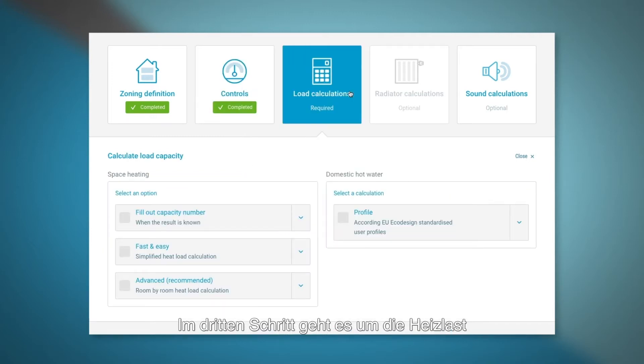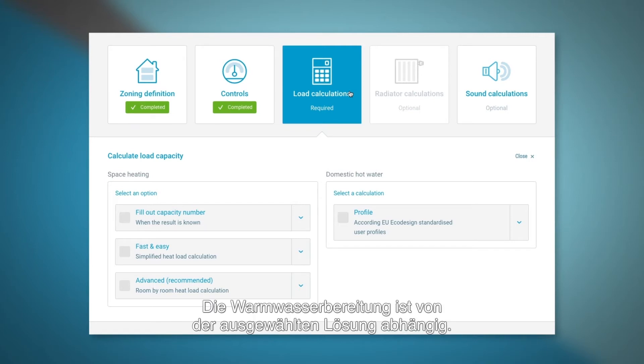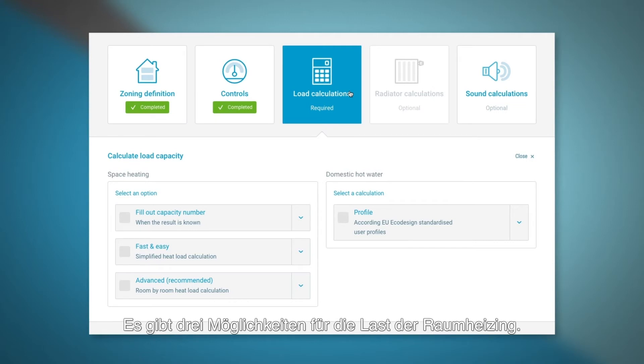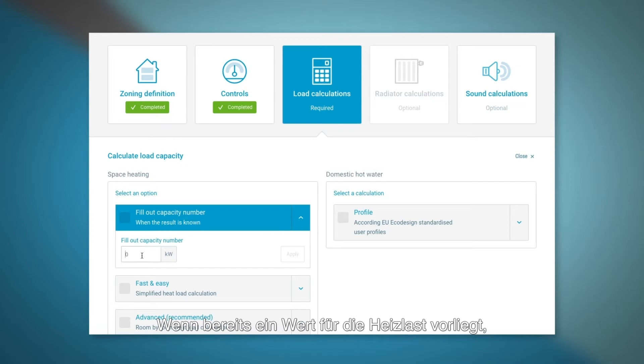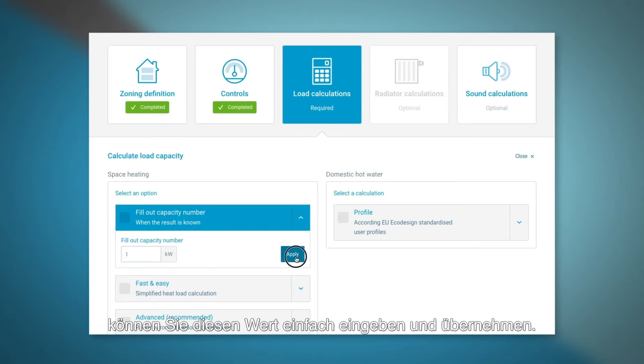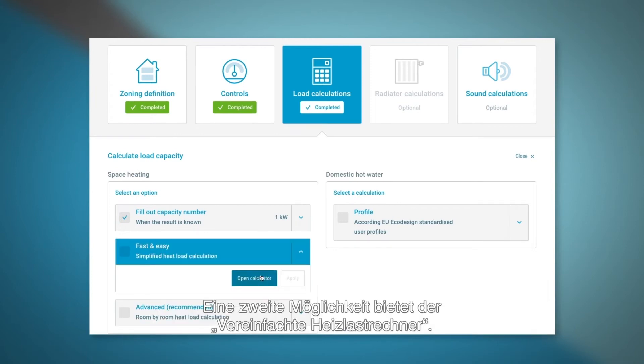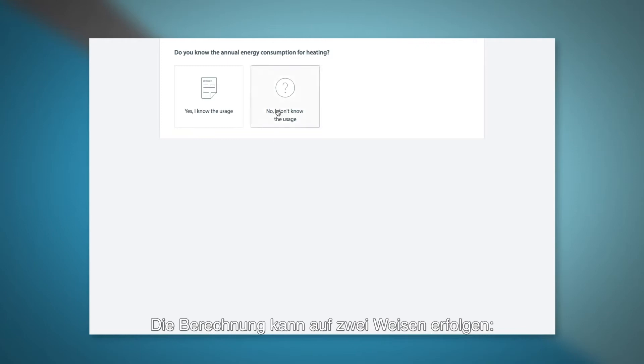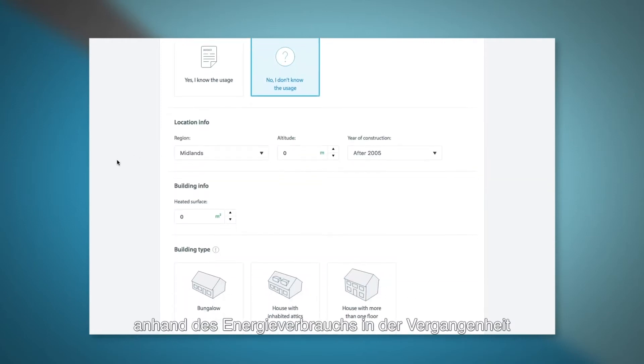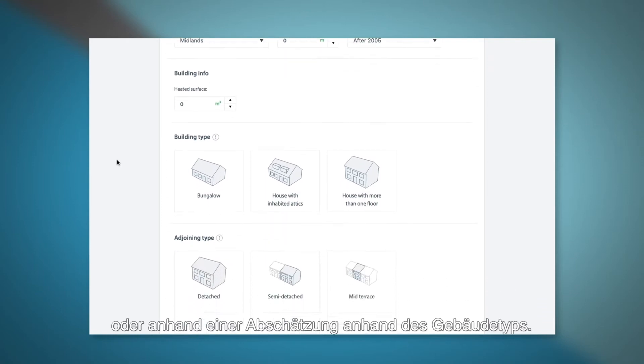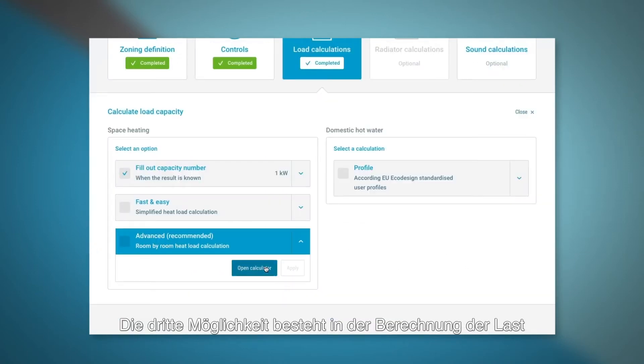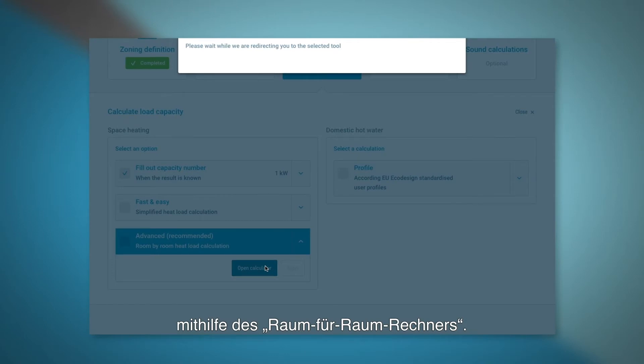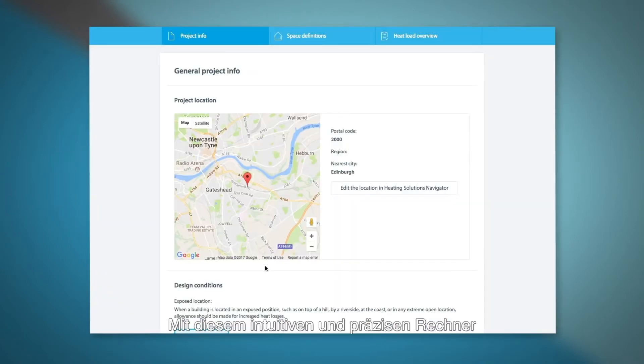The third step is the heat load for both space heating and domestic hot water. Domestic hot water is optional depending on the selected solution. Space heating load can be defined in three ways: if you have a heat load value already provided, you can simply enter the value and apply. The second option is the simplified heat load calculator tool, which can be completed either from historical energy consumption or an estimate based on the house type. The third option allows you to calculate the heat load using the room by room calculator, which is an intuitive and precise calculation tool allowing you to produce an accurate heat load.